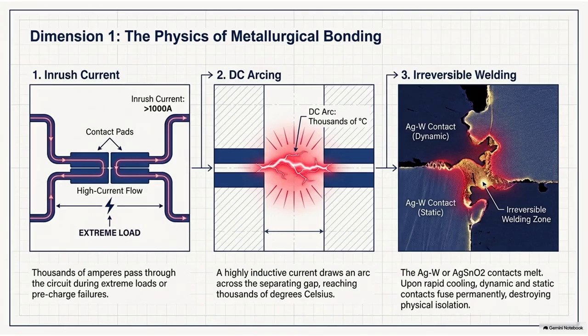That is a highly accurate mechanical parallel. Because in the electrical realm, an empty DC link capacitor has an effective resistance of near zero. Oh, wow. Yeah, it represents a massive electrical vacuum. If the main contactor were to simply slam shut while that capacitor was completely empty, the sudden rush of electricity from the battery trying to fill that vacuum, what we call the inrush current, would be astronomical. Because it's trying to fill it all in a millisecond. Exactly. It would instantly exceed the physical current carrying limits of the relay, creating the exact same extreme localized heat, melting the silver alloys, and forging that exact same metallurgical weld we saw with hot switching.